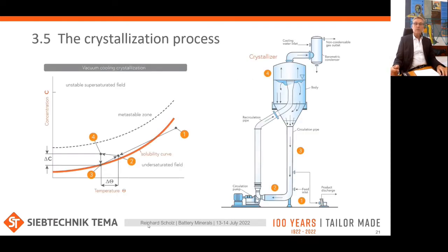This slide shows how to generate and control supersaturation in a vacuum cooling crystallization process. On the right, you see an FC crystallizer with an outside recirculation pipe and a recirculation pump. This keeps crystals in suspension, and the flow also serves to adjust the degree of supersaturation created here and distribute it evenly within the crystallizer. On the left, a solubility curve diagram is shown. The red line marks the solubility curve. The metastable zone extends till the dashed line, where spontaneous nucleation will occur.